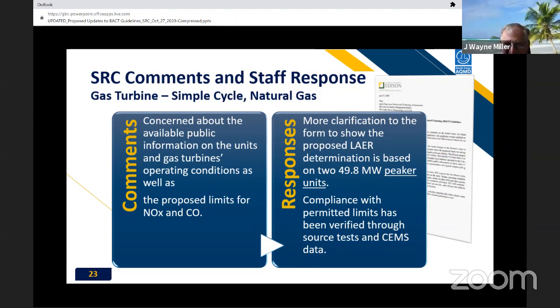Okay, Gary, question? Yeah, I just want to add that the effect of this change in the BACT level will be to shorten catalyst life. It's always a trade-off between NOx and ammonia slip. You always start with, as Sean mentioned, a comfortable compliance margin to allow for catalyst decay over time. There's no question that 2.3 ppm NOx and 5 ppm ammonia is technically feasible, but the practical effect is that you will require more frequent catalyst replacement.